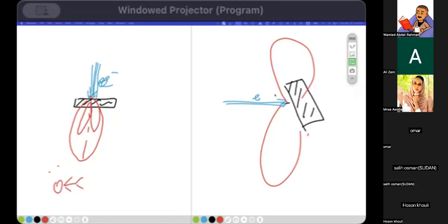Okay, Dr. Wahid, I have another question. One of my colleagues asked me about a problem that happened in their unit. They changed the gun of the accelerator. When they change the gun of the accelerator, will there be any change in the resulting photon beam? Do they have to do special checks? Is the quality, I mean the Dmax of the photon beam, going to change? Dmax is not really sensitive.